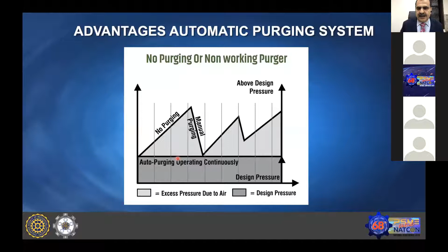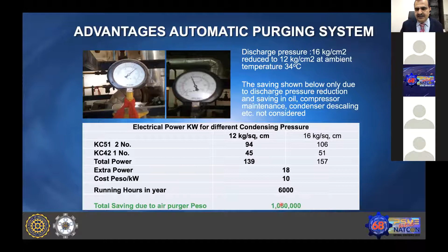So in case of automatic purging, this level is continuously maintained at design pressure, and it saves a lot of energy. This is a typical example showing the actual installed performance of an air purger. Here the pressure was almost 16 kg, and after installing the purger, it came down to 12 kg. So the power dropped from 157 kilowatt to 139 kilowatt, and total saving in a year was almost 1 million peso.